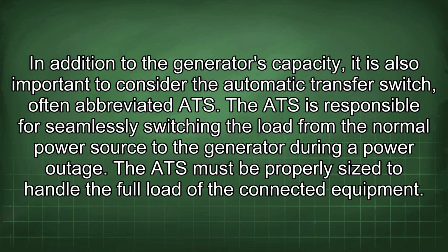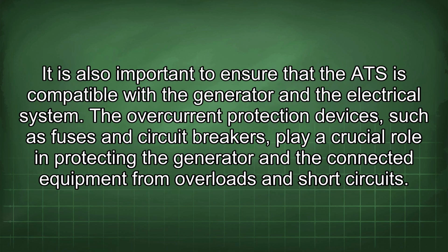In addition to the generator's capacity, it is also important to consider the automatic transfer switch, often abbreviated ATS. The ATS is responsible for seamlessly switching the load from the normal power source to the generator during a power outage. The ATS must be properly sized to handle the full load of the connected equipment. It is also important to ensure that the ATS is compatible with the generator and the electrical system.